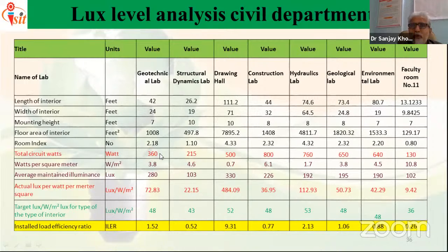That means how many tube lights are fitted inside that particular laboratory, the total summation of all. Suppose one tube light is 40 watts, so 40 watts multiplied by the total number comes to 360 watts. Then we calculate watt per square meter, since we know the area. So watt per meter square comes to 3.8. That means for that laboratory, the consumption is 3.8 watts per meter square. This is the connected load.